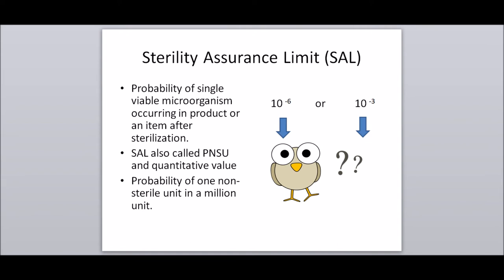Sterility Assurance Level, or SAL: the probability of a single viable organism occurring in a product or an item after sterilization. SAL is also called the probability of a non-sterile unit. The term SAL takes a quantitative value, generally 10 raised to minus 6 or 10 raised to minus 3. A SAL of 10 raised to minus 6 means the probability of one non-sterile unit in one million units.